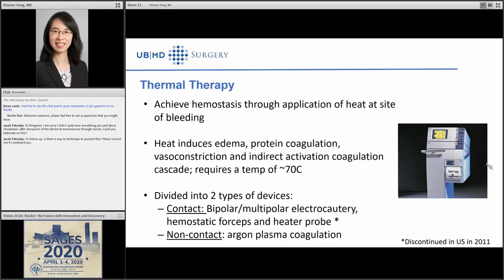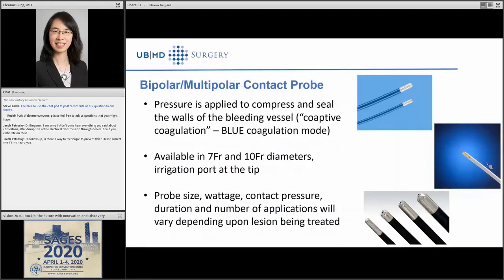Non-contact thermal therapy is argon plasma coagulation. In terms of the contact probes, this is where pressure is directly applied with the probe to compress and seal the walls of the tissue, the bleeding vessel, and we use the blue pedal to coagulate the vessel. They're available in both 7 French and 10 French diameters, depending on the scope that you have.